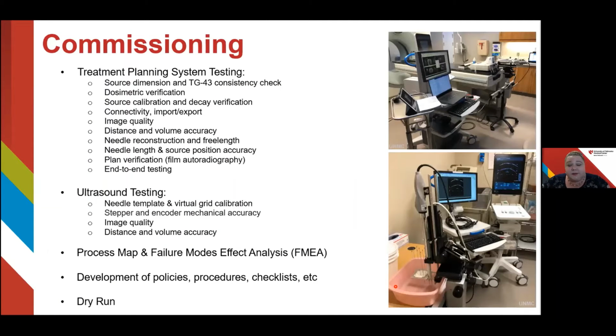So next you'll need to perform a series of commissioning tests to ensure the functionality and accuracy of your treatment planning system, as well as your ultrasound system. Most of these tests are actually pretty similar to all the commissioning tests you'll need for any brachytherapy program, but there are several unique aspects such as the template calibration, the stepper mechanical accuracy, connectivity between the planning system and the ultrasound, and then the ultrasound image quality.